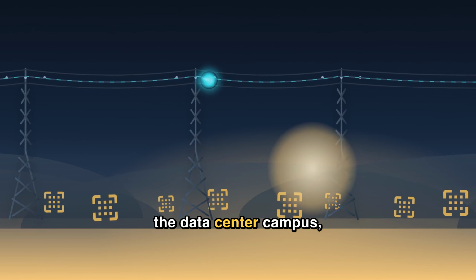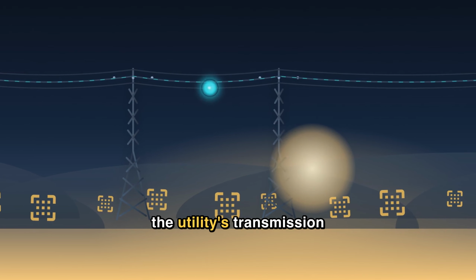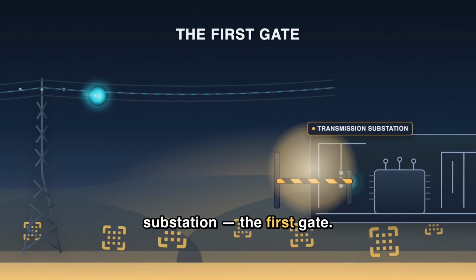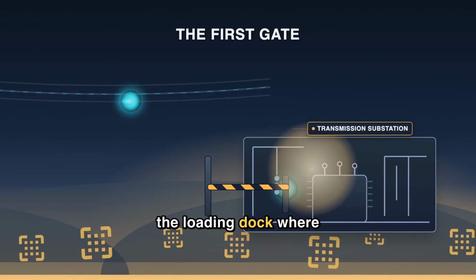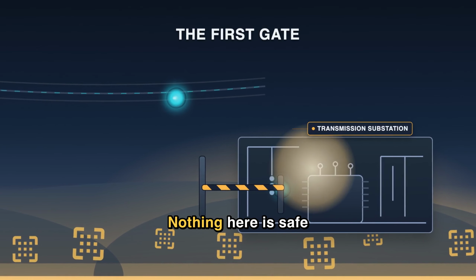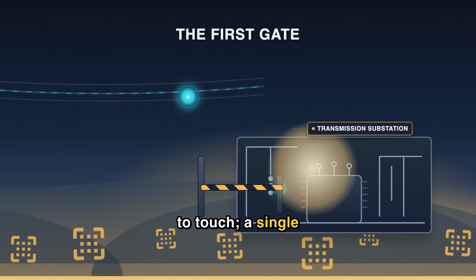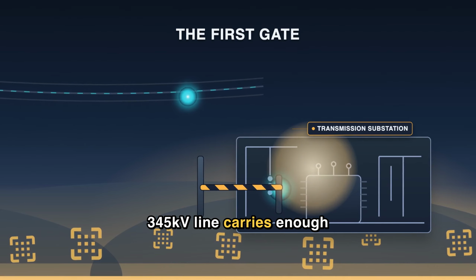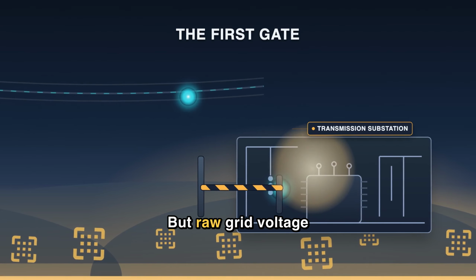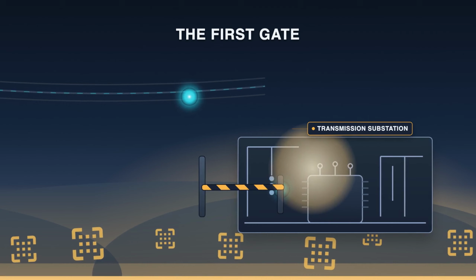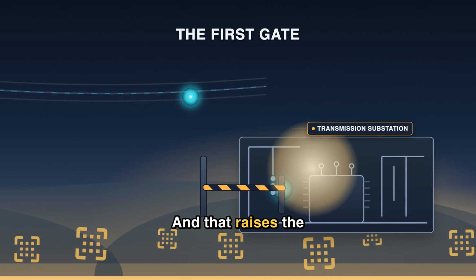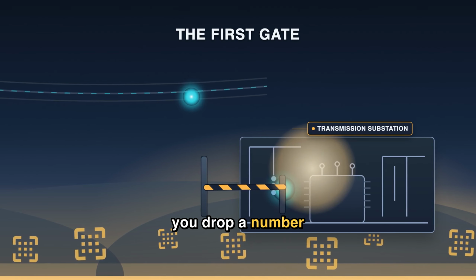At the edge of the data center campus, it finally arrives at the utility's transmission substation, the first gate. Think of it as the loading dock where raw grid power pulls in. Nothing here is safe to touch. A single 345 kilovolt line carries enough to vaporize metal. But raw grid voltage is useless to a chip. It has to come down. And that raises the next question. How do you drop a number that big?